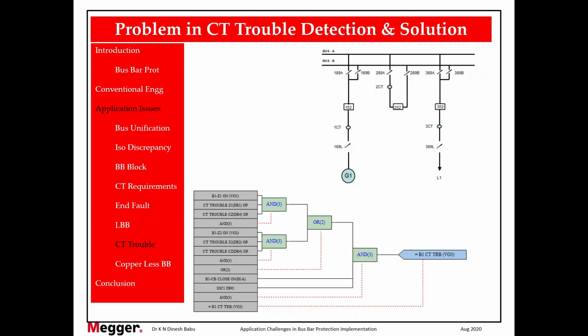Now for the second bus, Bay 1 in zone 2, CT trouble in zone 2, check zone, CT trouble has picked up.